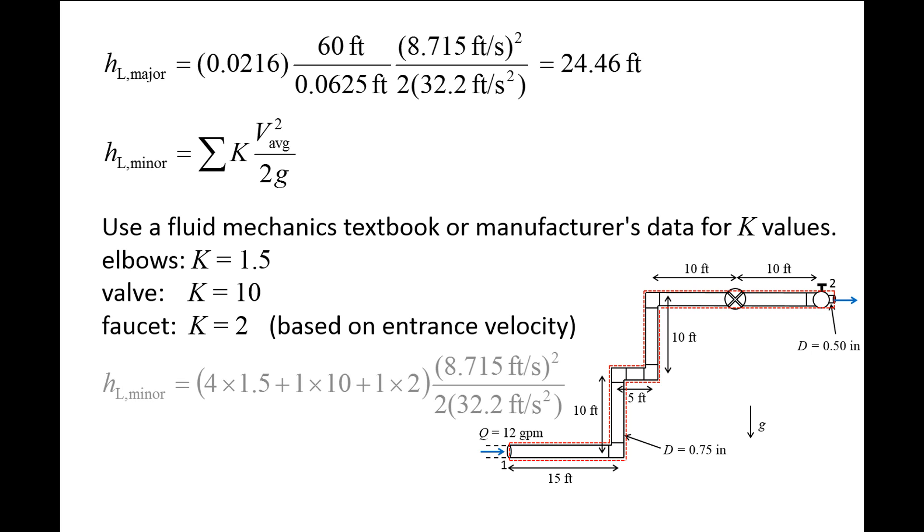We can now calculate the total minor head loss for this system. Since the same flow speed is used for all components, we can add up all the loss coefficients and multiply by the average speed squared over 2g, giving us a minor head loss of 21.23 feet.